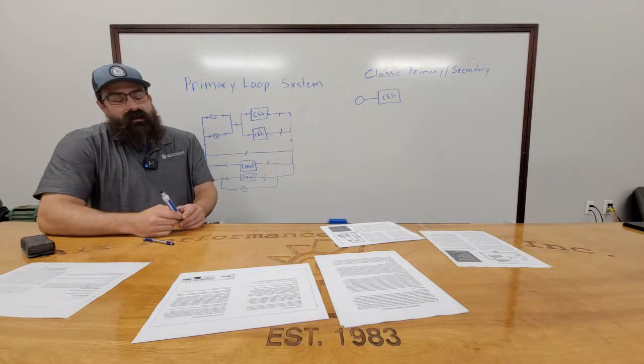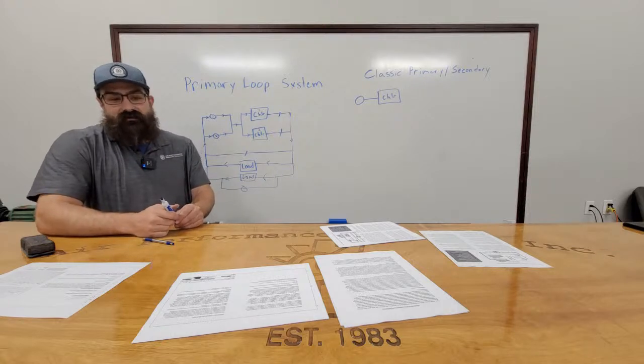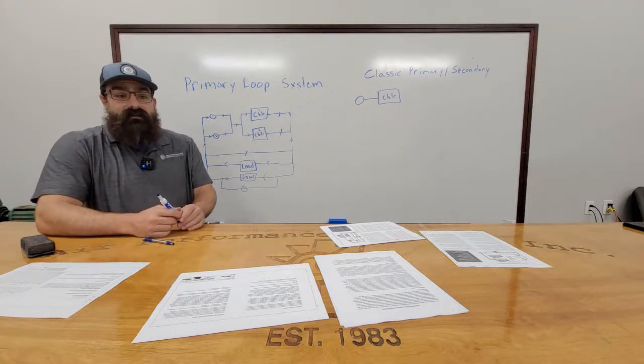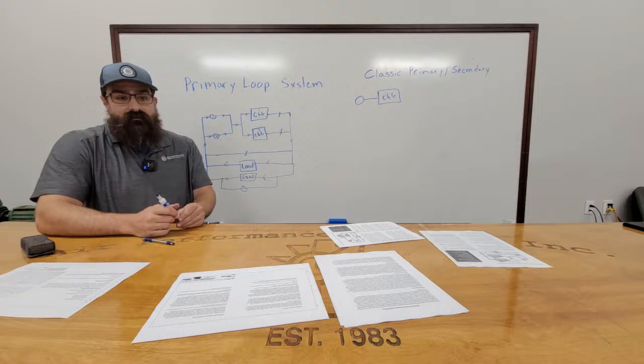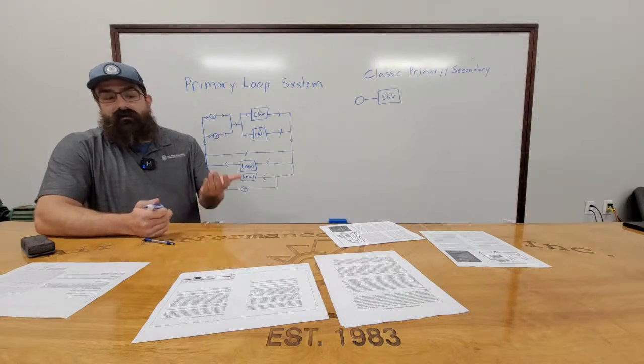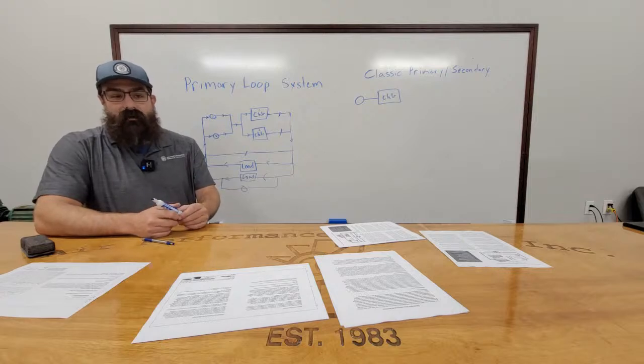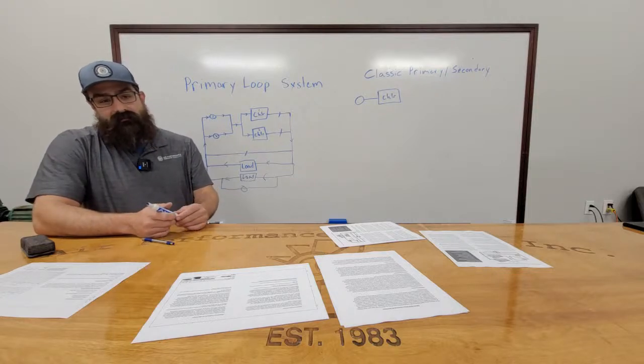But I would just have to see the situation you're talking about. It's probably unbalanced. And I pretty much guarantee it's unbalanced. But we could hire a TAB contractor and have them come do a water balance on the system. It's going to be expensive.